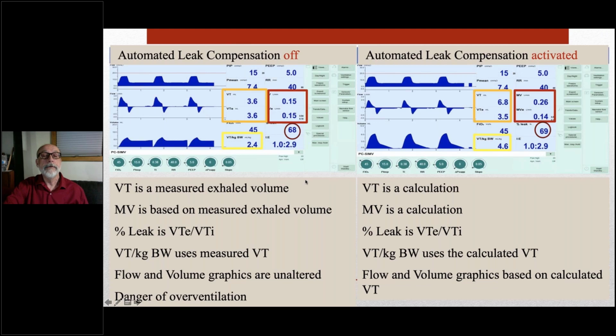So here is another way of looking at things. When you do not employ leak compensation, it is off here. You can see there is a very large leak in this example, about 2/3. And so the exhaled tidal volume that's measured is 3.6 ml in this example.